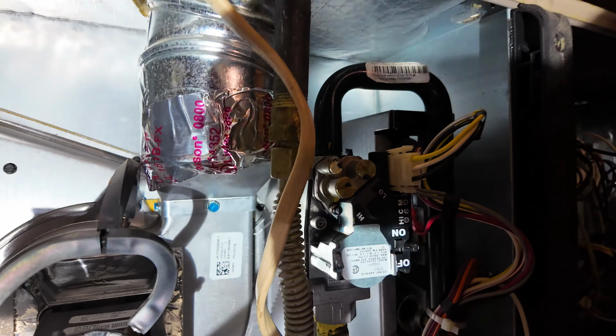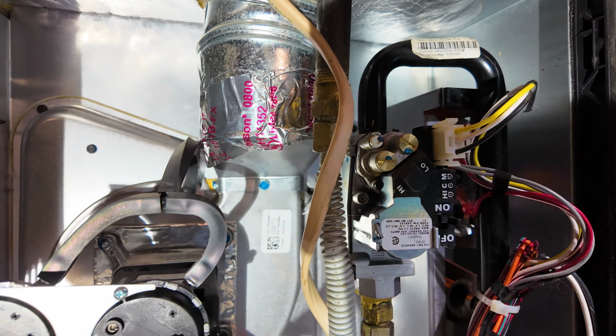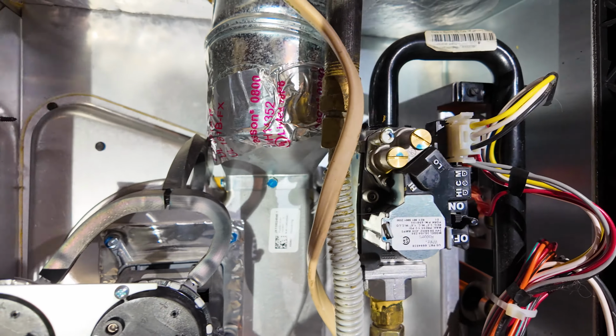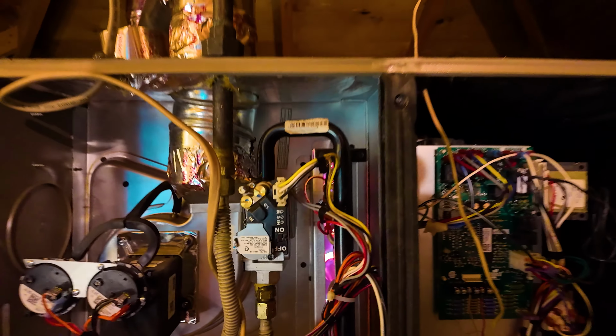Okay. You hear the inducer fan came on to start the draft going. And it does that first. Okay, now the red igniter's coming on. You can see that back in there. You kind of see them in there. So you can see them as best we can. They're hard to see exactly. That's gas fire burning in there. And all the burners are on. And so it looks good. Nice blue flames. Now it's operating properly.